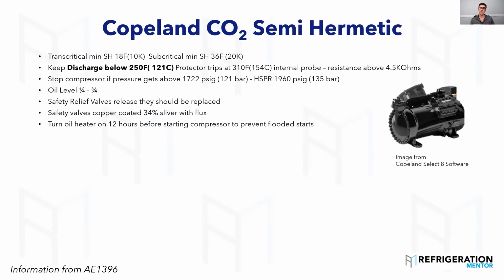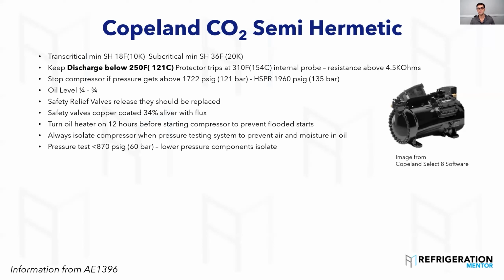joint. Turn on oil heater 12 hours before. And this is to prevent flooded starts, similar to what Bitzer says. Always isolate the compressor when pressure testing to prevent air and moisture in oil. Same thing as the other compressor manufacturers. It's important. And you'll see over time when you're working, you're starting to read these guides, you're going to see a lot of similarities. There are going to be different uniqueness, like, you see the discharge, keep the discharge below 250 compared to a Bitzer, but you're going to see a lot of uniqueness. You want to keep moisture, you want to keep air out, you want to be running that oil heater before.